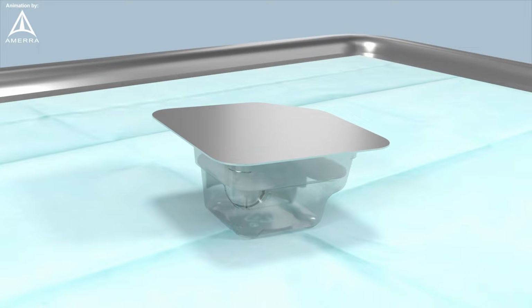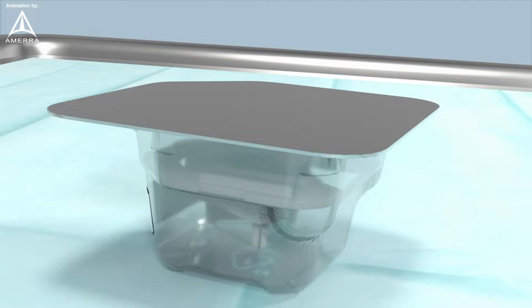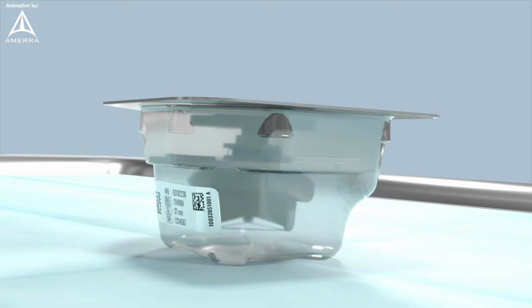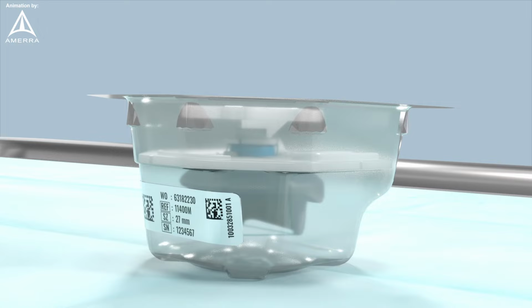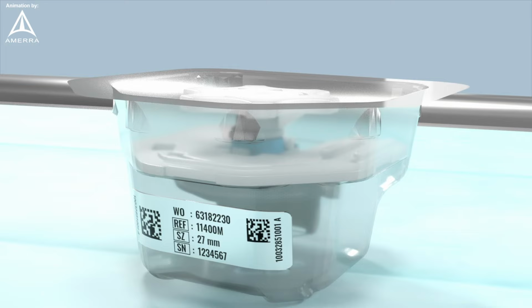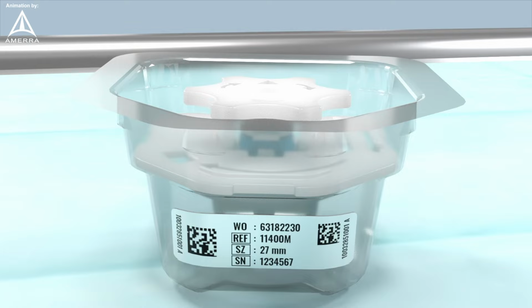The contents of the inner tray must be handled using a sterile surgical technique to prevent contamination. In the sterile field, examine the inner tray and lid for evidence of damage, stains, and broken or missing seals. Hold the base of the inner tray and peel the lid from the inner tray. Verify that the serial number on the silver label matches the shelf carton and implant data card.